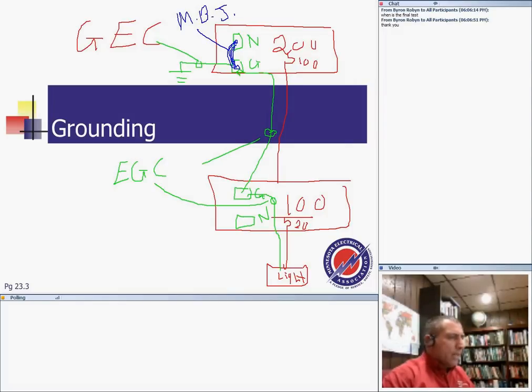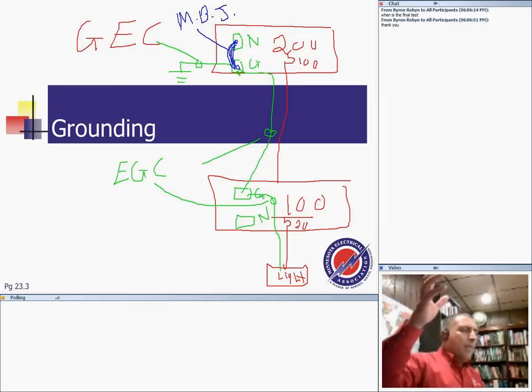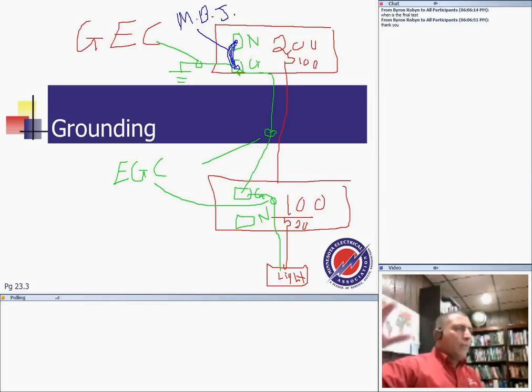The question is, what's the bonding in the transformer? There are two bonding jumpers. One is called the main bonding jumper. You do this one at the service. And the second one is the system bonding jumper. That's the one that you do at the transformer of a separately derived system. So if you have a 480 208 120 and you bond the neutral to the ground at the 208 120, that's called the system bonding jumper.